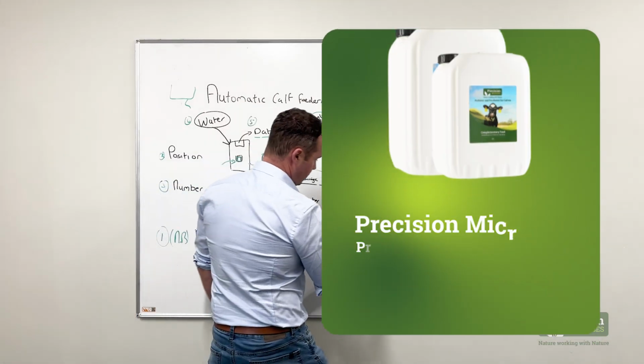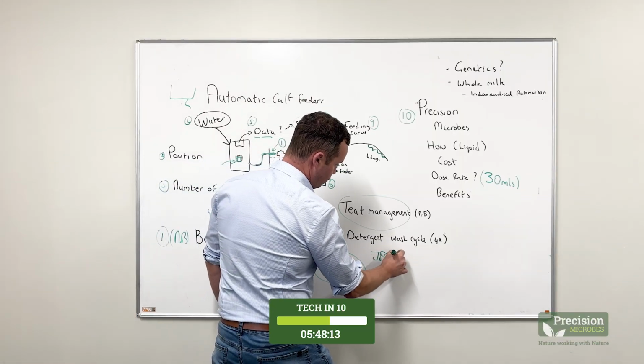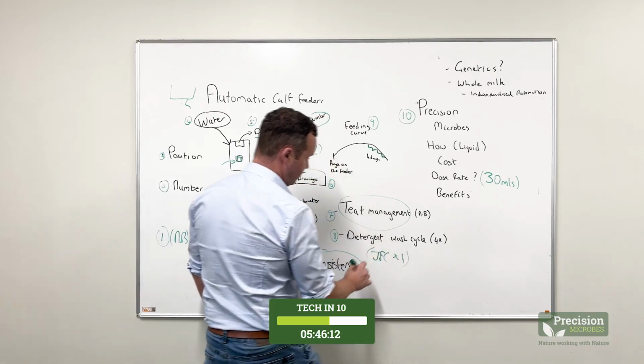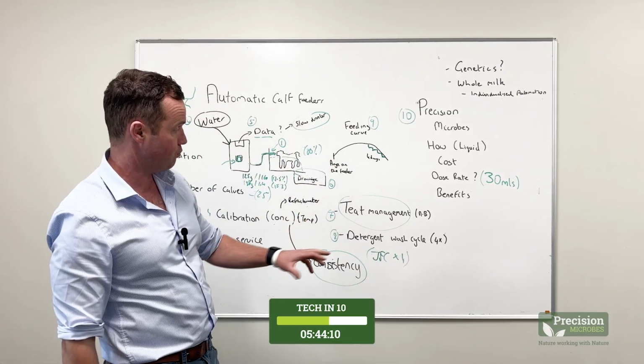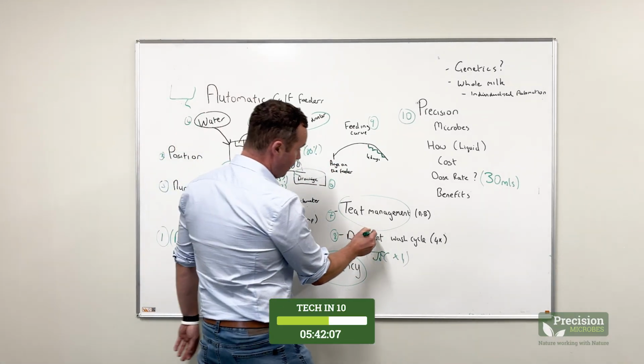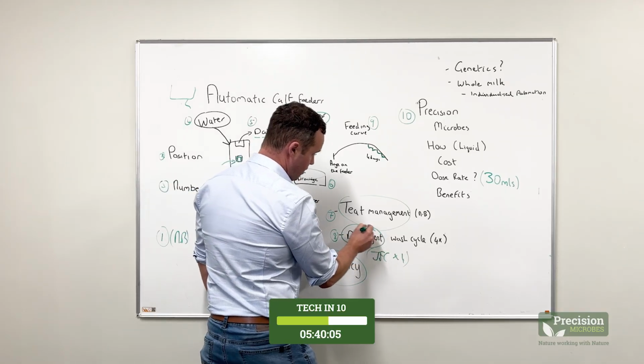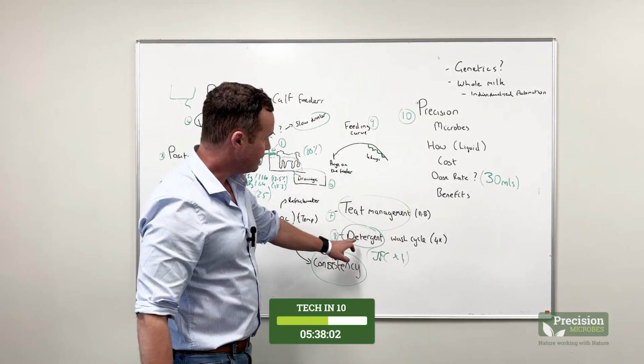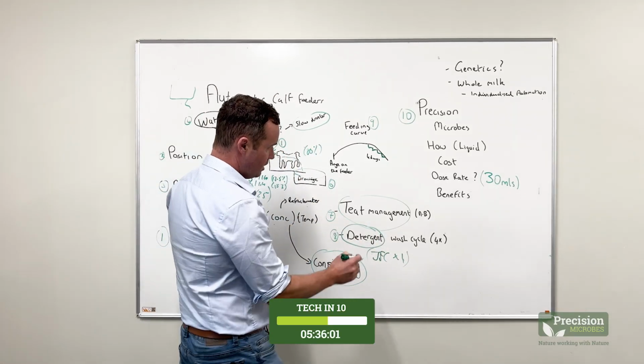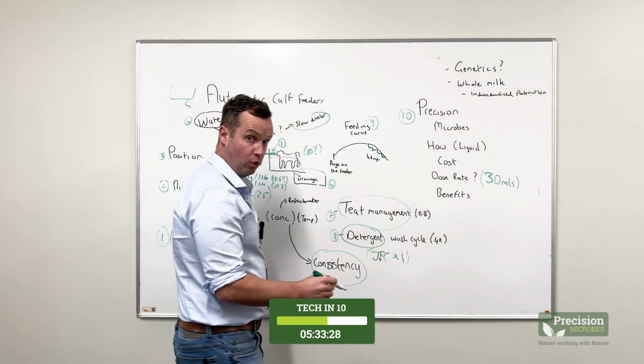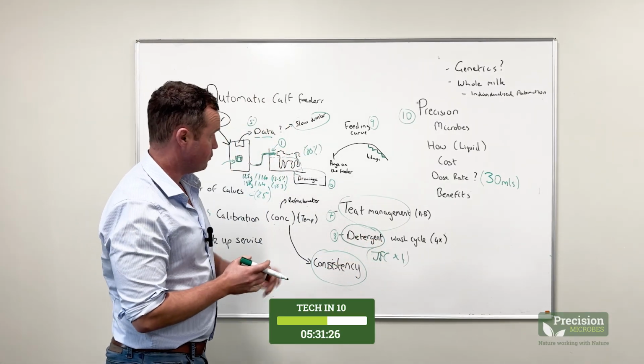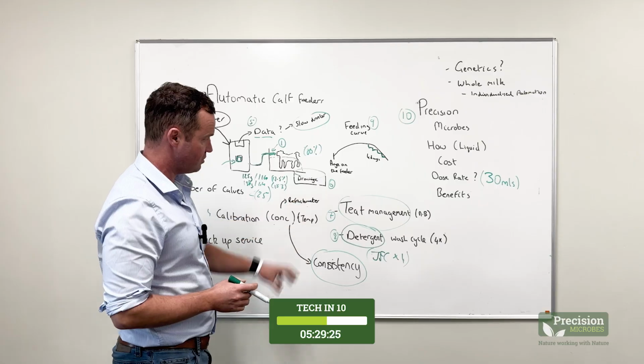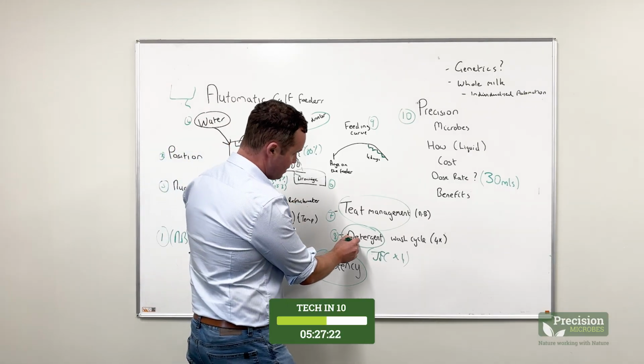Having good wash cycles. So, for example, just from a machine I know, JC has 4 automatic wash cycles. A lot of the modern machines will have regular wash cycles. Now, that will require a detergent, or generally a detergent. It can either be alkaline or acids. Just make sure that the detergent is the correct one and it's at the correct temperature. So different machines will have different temperatures and wash cycles, and that the detergent matches the challenge.